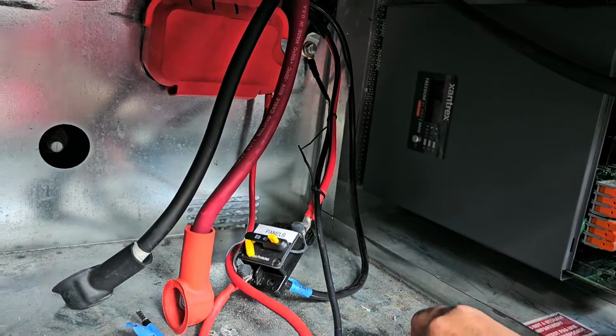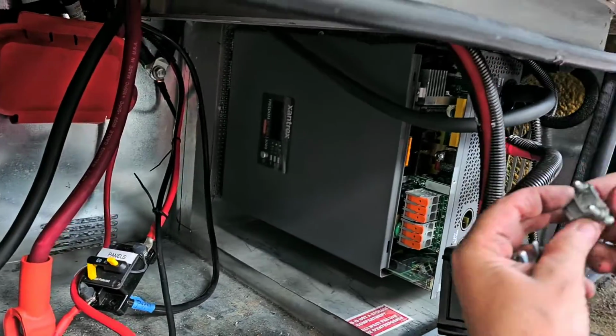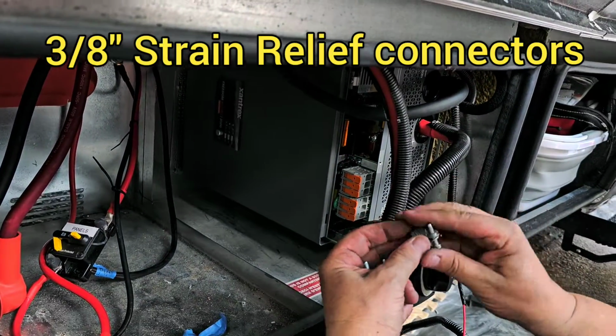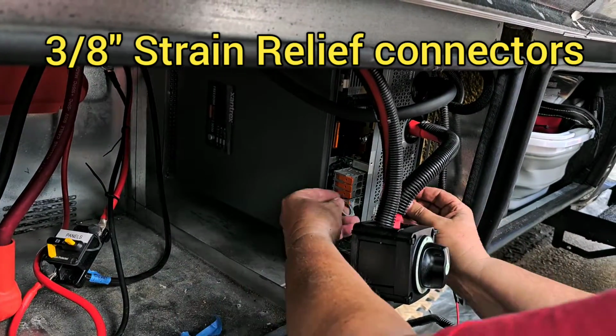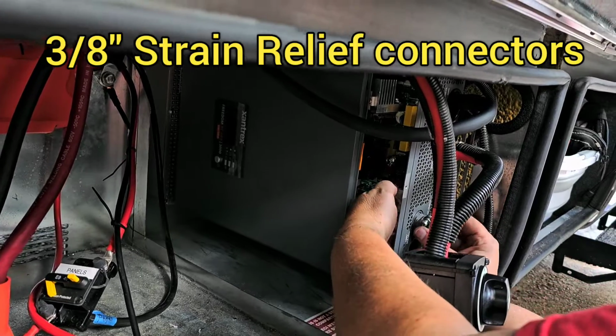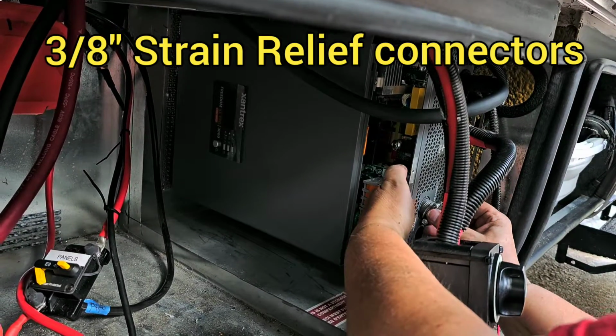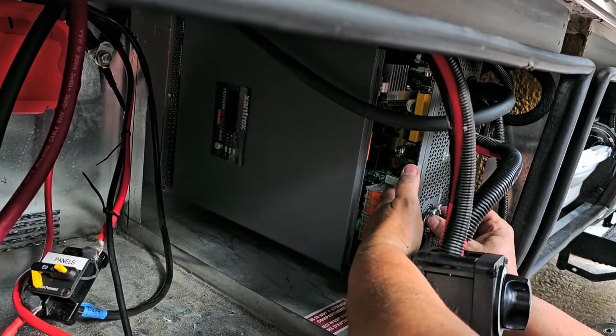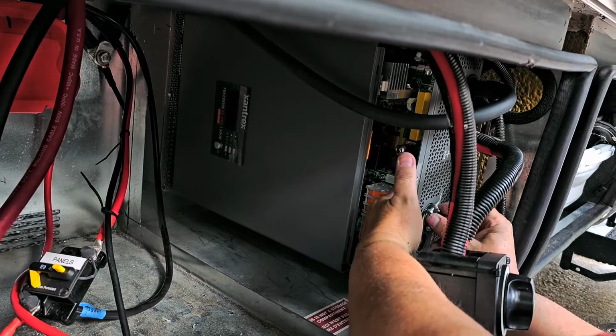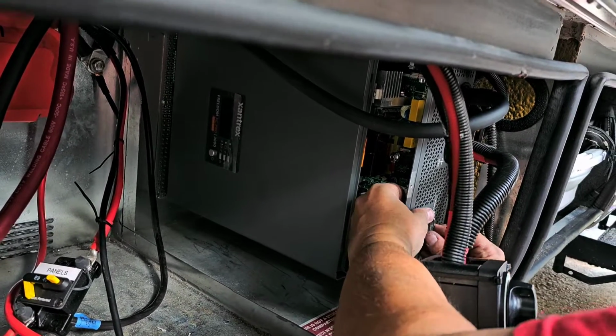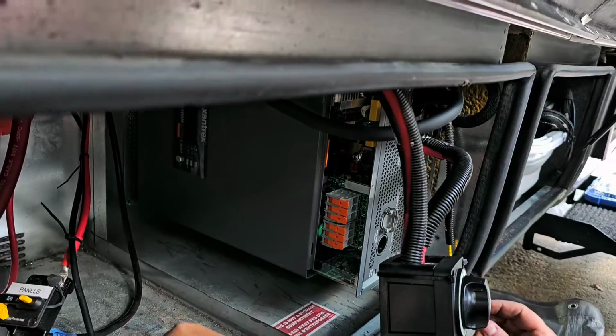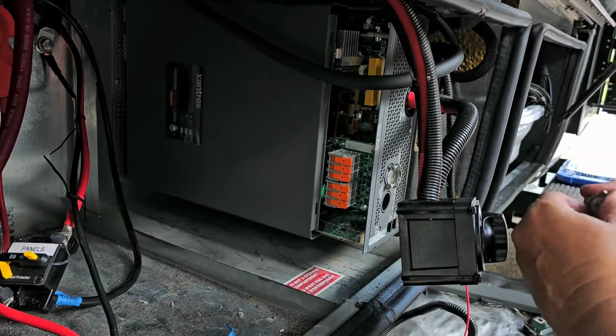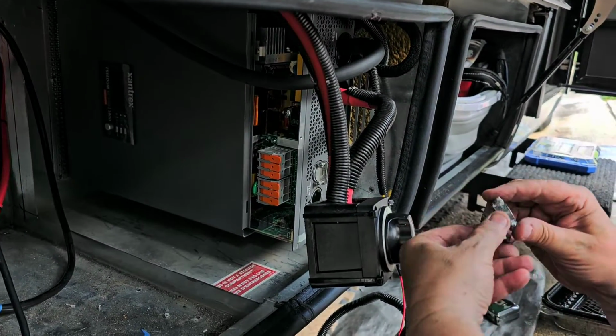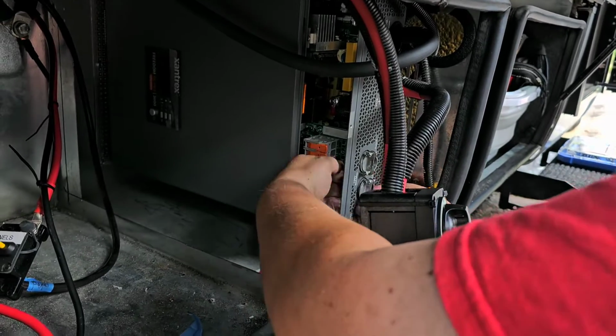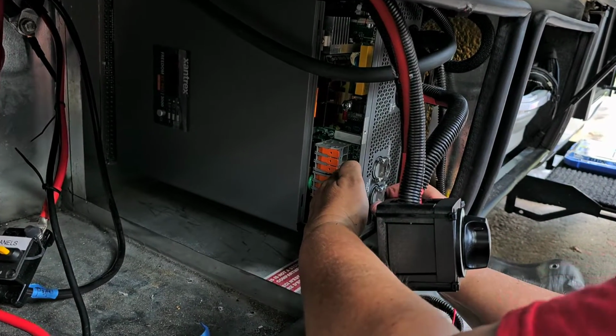Oh, now I have to put on these little connectors for when we run the 120 AC wire, which is a 10-gauge Romex, 10-2 with ground. So we're going to use these to stabilize the wires in the inverter.